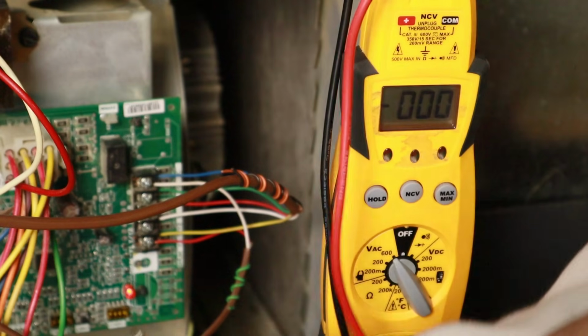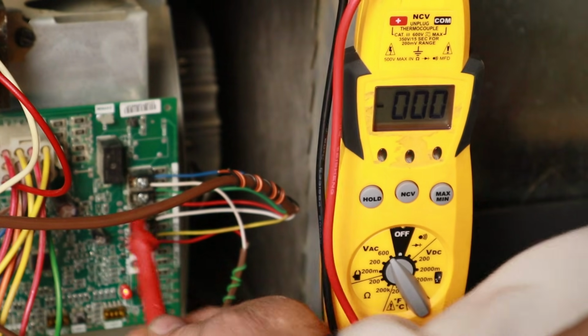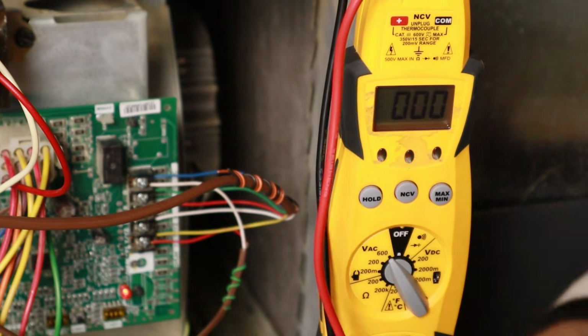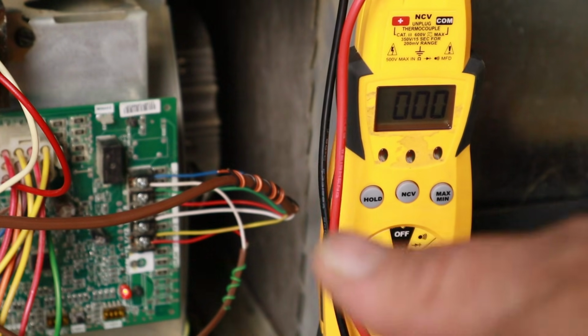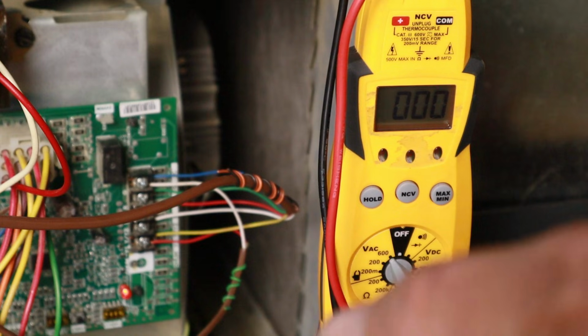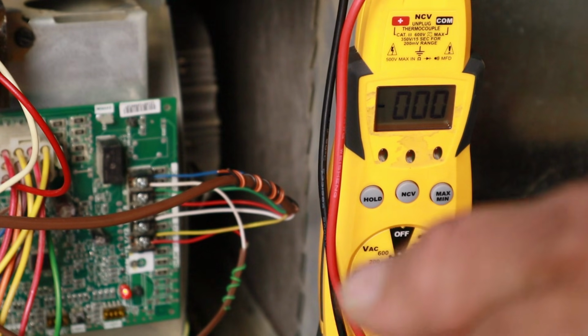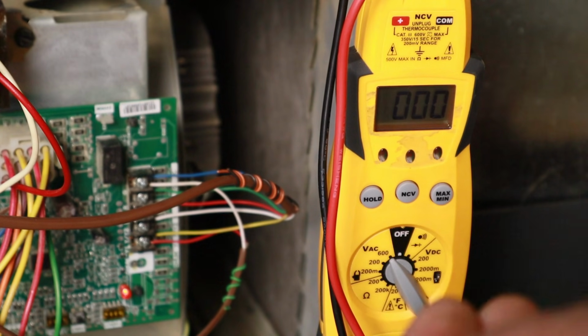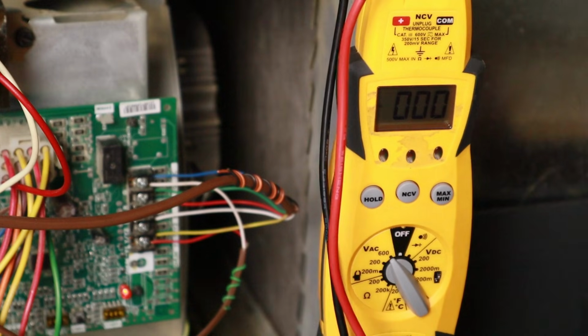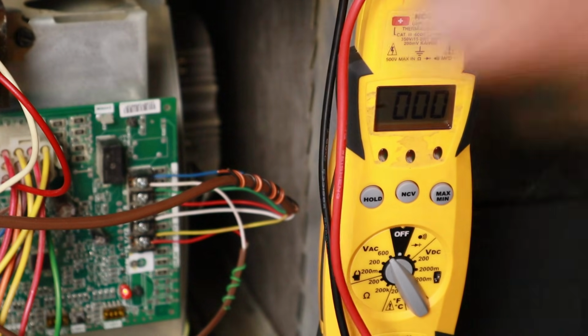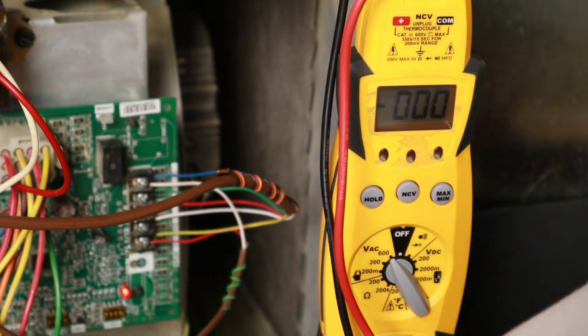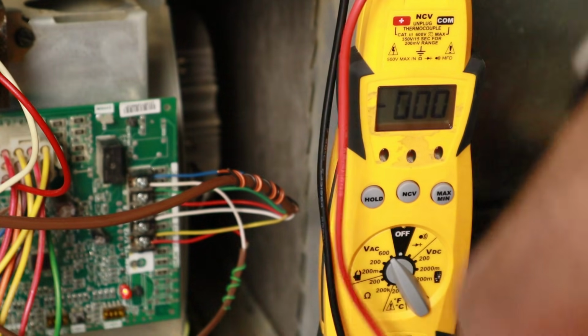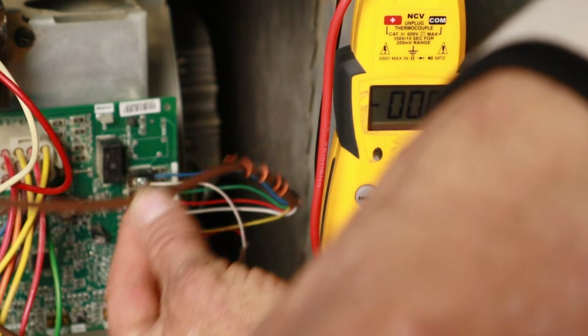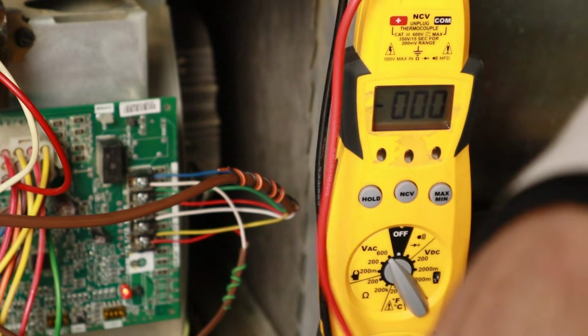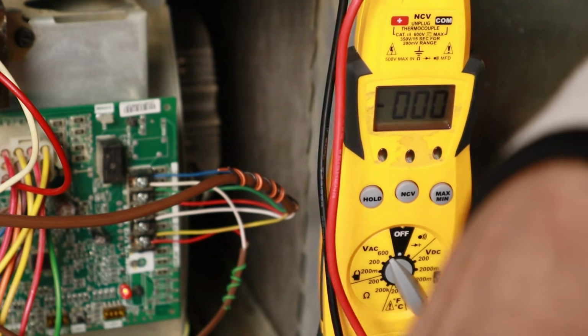So going back to our R terminal here, this is the wire that goes up to the R terminal in our thermostat. And this is essentially the beginning of our low voltage control circuit that is not going to be in our wiring diagram, because the wiring diagram only covers the wiring inside the unit itself. It doesn't cover what's called field wiring. So your thermostat wires here going up to your thermostat is basically field wiring. And that's something you just have to know.